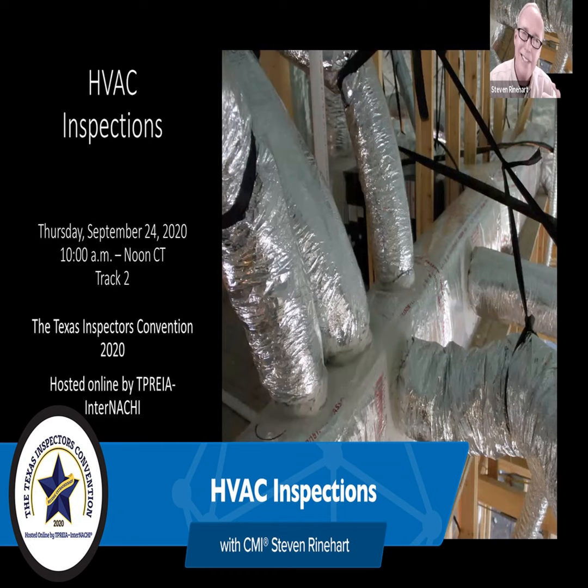Condensing units lacking adequate clearance, air circulation. We're talking outside. Manufacturers have different requirements. The smallest place I've seen, 6 inches. Some of them, they'll say 6 inches on one side or 2 sides and open on the other. You just don't want to see one right up in a corner, real close to the house and maybe a fence. I mean, think about it. It's sucking air in the sides and out the top. And more air is better.